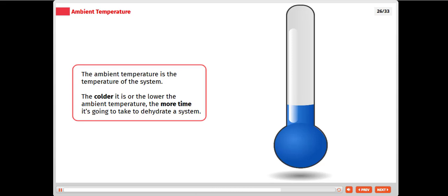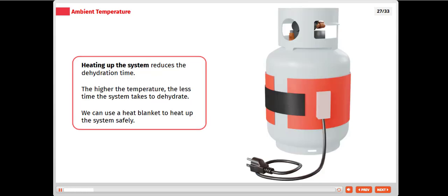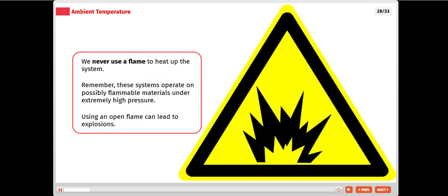Heating up the system reduces the dehydration time. The higher the temperature, the less time the system takes to dehydrate. We can use a heat blanket to heat up the system safely. We never use a flame to heat up the system. Remember, these systems operate on possibly flammable materials under extremely high pressure. Using an open flame can lead to explosions.